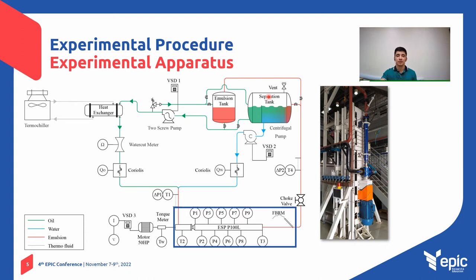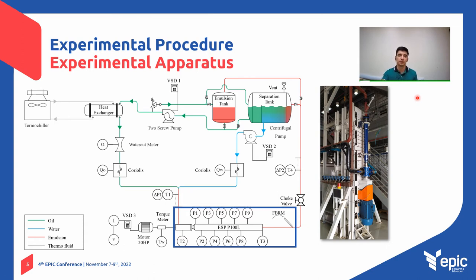The oil phase is drawn from the tank by two screw booster pumps and flows through a temperature control system composed of a shell-and-tube heat exchanger and a thermochiller. Temperature control is essential since the system operates in a closed loop and tends to heat up. In addition, the oil viscosity is adjusted through temperature control.